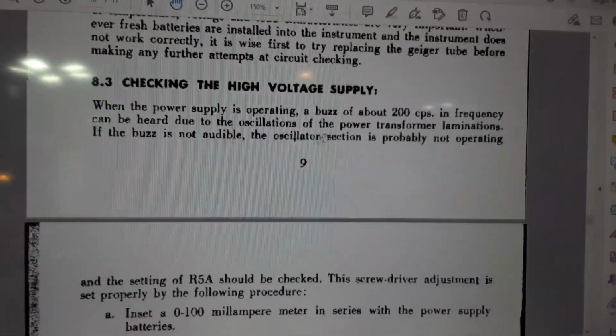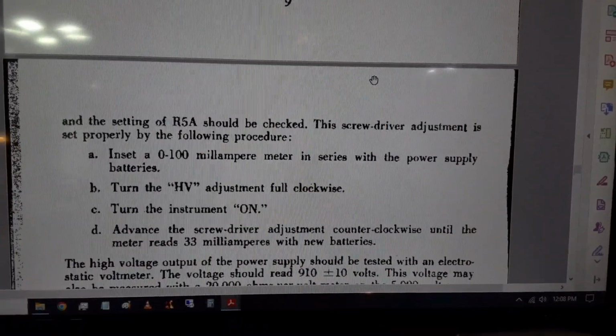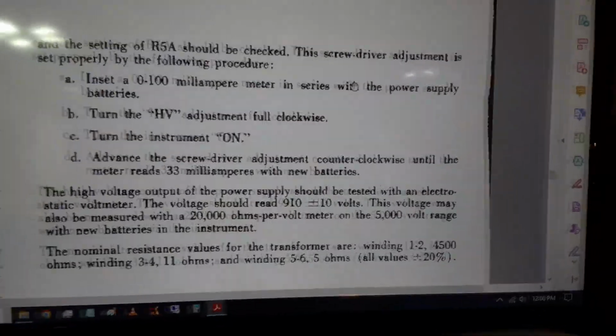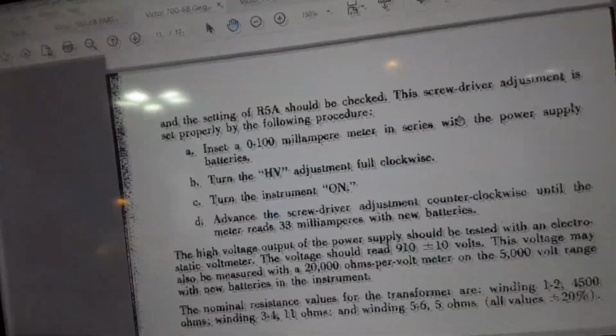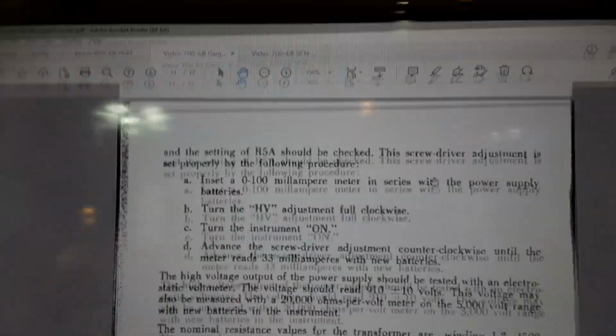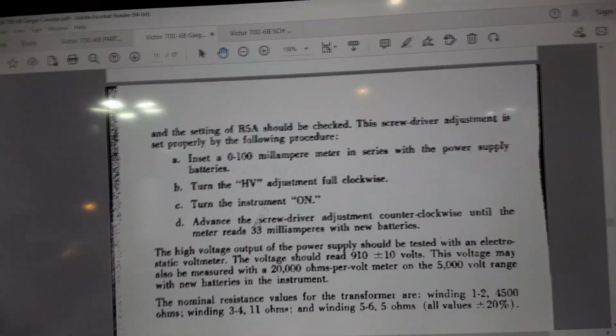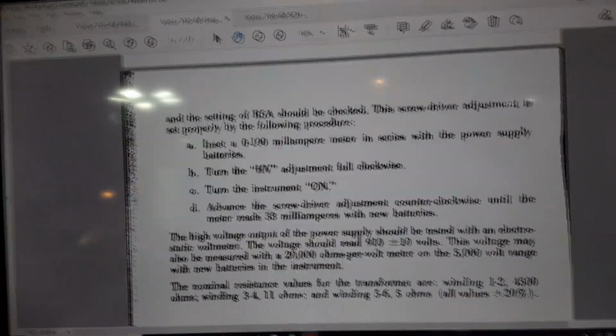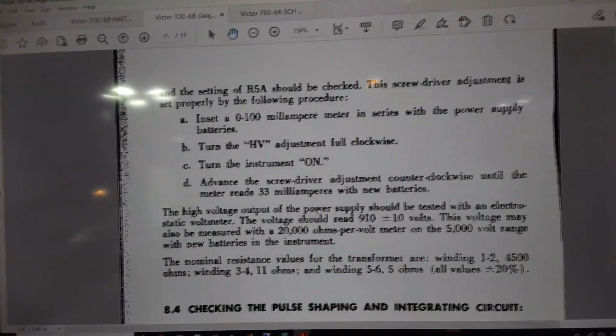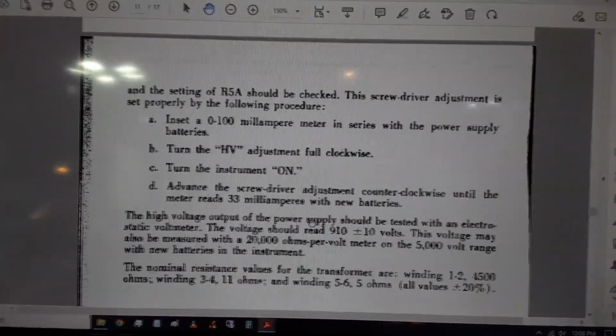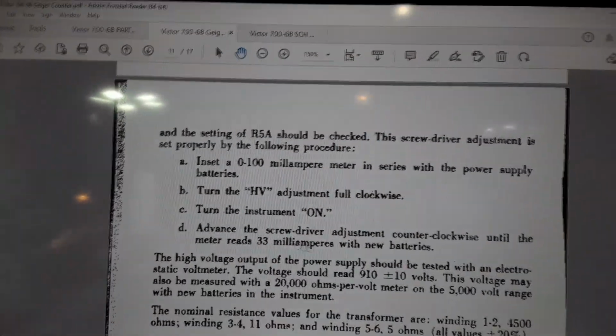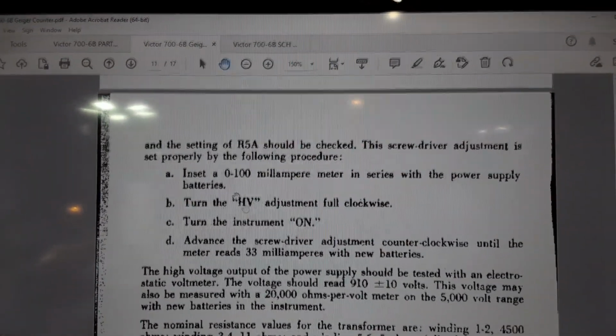And what we're going to calibrate is the high voltage. There's two ways to do the calibration on the high voltage. First off, if you don't hear that buzz that I was talking about yesterday in the last video, you know the high voltage is not working. Well, it is working. We are currently on. We can check it two ways, and this is the way we're going to do it. The other way would be to check the high voltage with a probe, but we're going to just check the current draw and make sure that we get the right current draw.